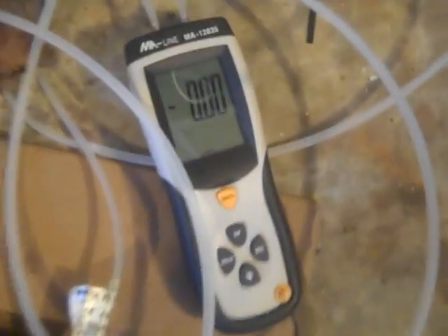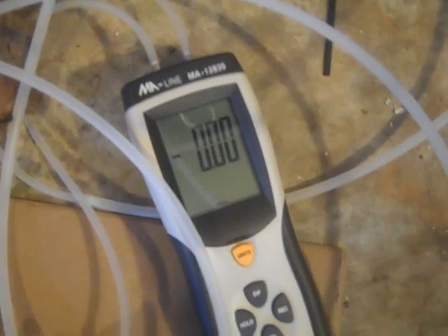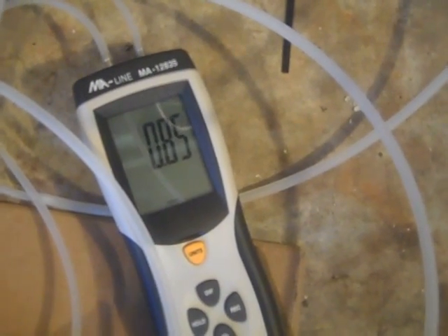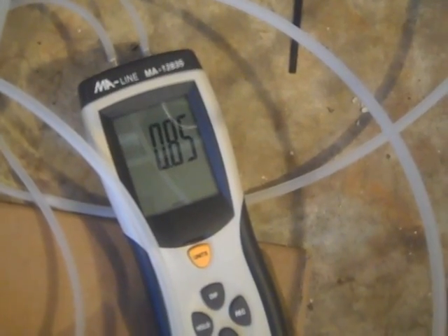I think you get the picture. We're going to do high next. And it is parked right now. That's going to be really close to .1, which is not going to be acceptable. But we're just doing, we'll go ahead and get all our readings. So, here we go. .85, .86, just flipping around there. Get the pencil. .86.